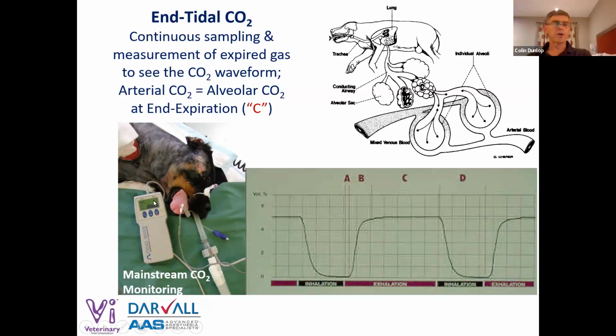And you can see, if you can look down and see on that monitor there, that was one of the early monitors we had that was a mainstream sampler, a very good monitor, and it's reading the CO2 in this dog of 44. There's the waveform on the screen. So you really need to see the end-tidal CO2 waveform to know that you've got a proper waveform when you are in fact getting end-tidal gas. And you can see some bumps on this one, which I'll talk about in a minute. And this is an artifact that we see in particularly small animals.